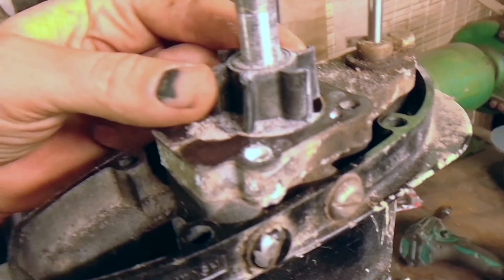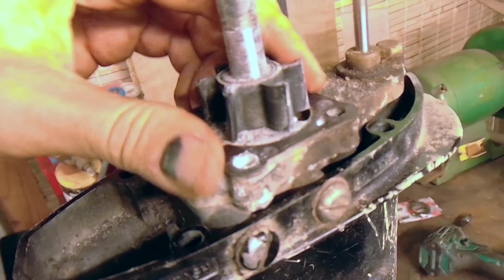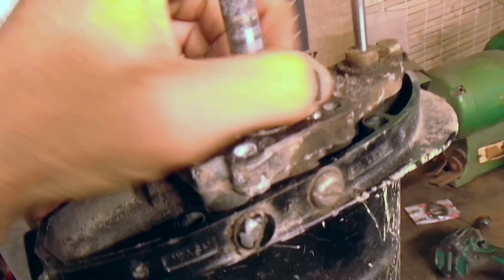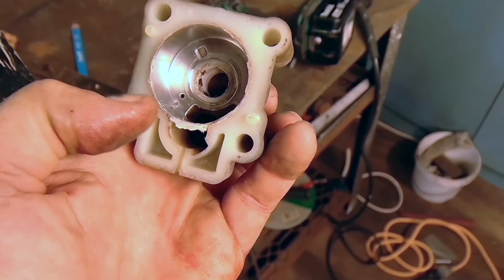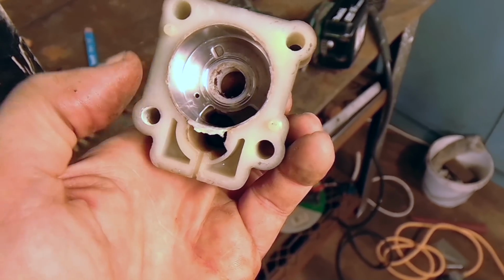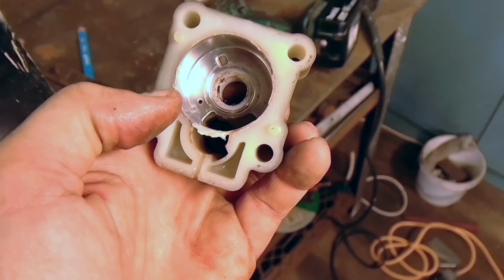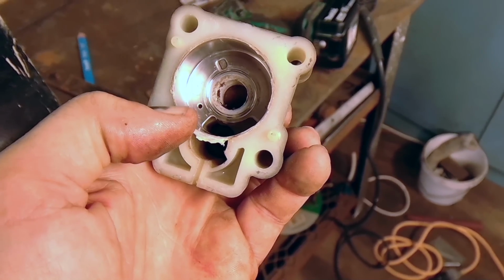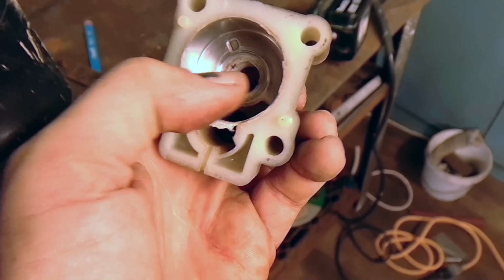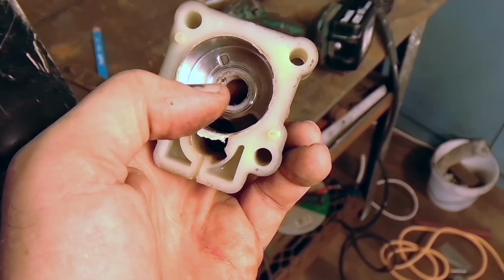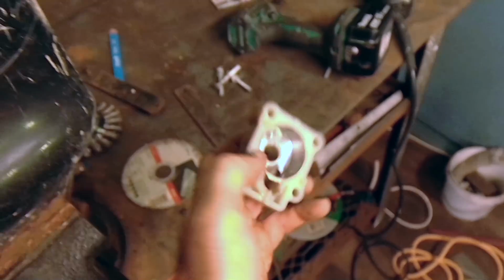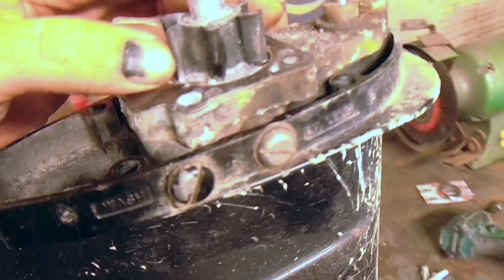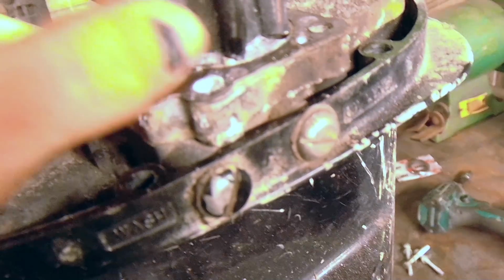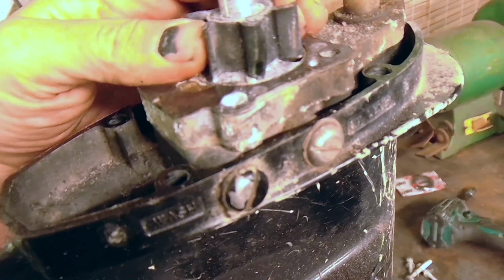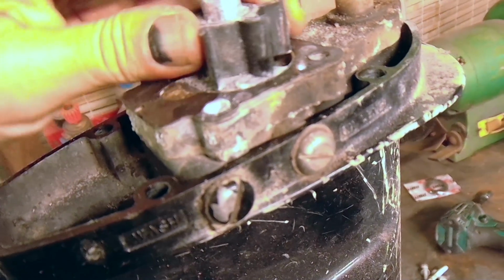Here's the little impeller, these flexible vanes, I believe they're neoprene. What makes this work is either a cam in one section, like you see in a Jabsco pump, or, in this case, the fact that the shaft's not centered on the cup. So the vanes up here are bent backwards more than the ones here, and when they open, they create a larger volume and therefore suck water and air, so they're self-priming to some degree.